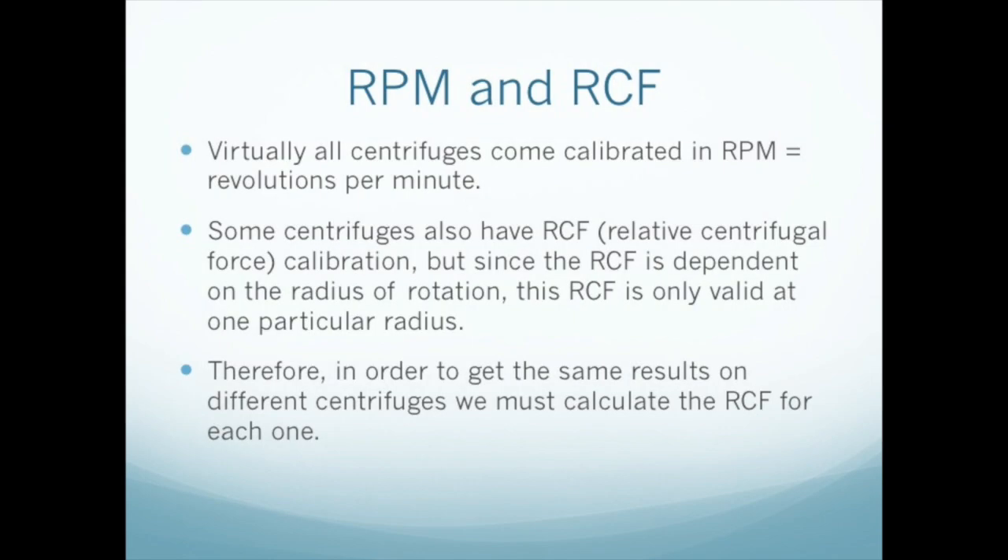Most centrifuges are not calibrated in G's, the unit of relative centrifugal force. So we need to be able to set the centrifuge in RPM — revolutions per minute. This is because the radius of each model of centrifuge is different, and the RCF is linearly dependent on the radius. Thus, 1000 RPM on your centrifuge will not give the same G-force as 1000 RPM on my centrifuge.